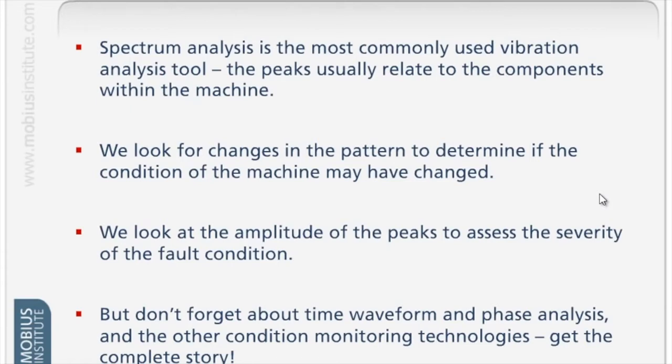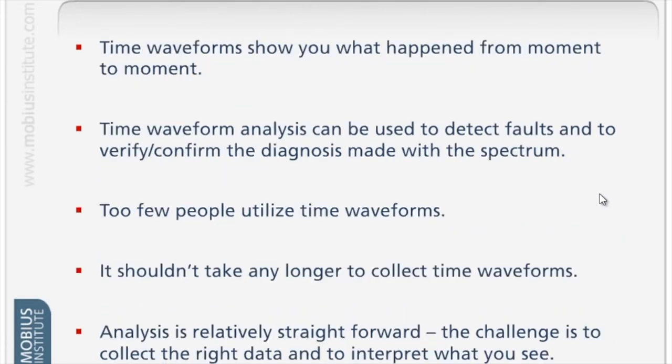But the time waveform and phase give us additional information, as do other condition monitoring technologies. Vibration is a condition monitoring technology; oil analysis, wear particle analysis, infrared, ultrasound, and motor current testing are all routinely checking the condition of the machine. Now, time waveforms show us what happened from moment to moment. It's like taking that movie and analyzing every frame of that movie. As the gears mesh together, is it going well? As the balls roll around, is it going well? It gives us that detail.